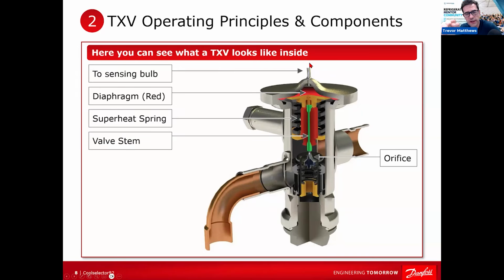But if you grab it and hold it and you increase the temperature of the bulb, what does it do to the pressure? Increase temperature, you increase pressure. And so what that does, it forces that gas and pushes down on this diaphragm to push on the pin, to open it up. And like Jamie says, you take that spring down at the bottom and you tighten up that spring and there's like a little plate. I don't know what you call that. I call it a pressure plate, but yeah. The pressure plate. So that's on the spring. And now we're pushing up against that pin. So we're fighting the diaphragm, not fighting, but we're trying to match that. Yeah, they're trying to find a balance. So it's always trying to find what we call an equilibrium, which is a fancy term for saying that things don't really change much.